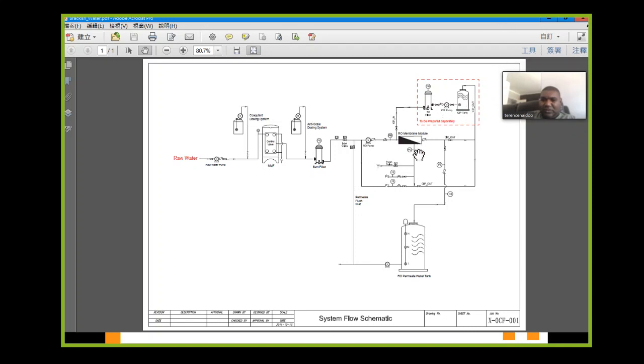But basically, when the tank is full, in a typical system, we just run flush, right, for 30 seconds before we shut down. It's automatic. But instead of that, we close this valve, open this valve, then let the water in, because this has a high pressure switch. When this opens, the high pressure switch releases, and the pump starts to run automatically. Water comes in. Then the flush valve opens, and water comes out like this.